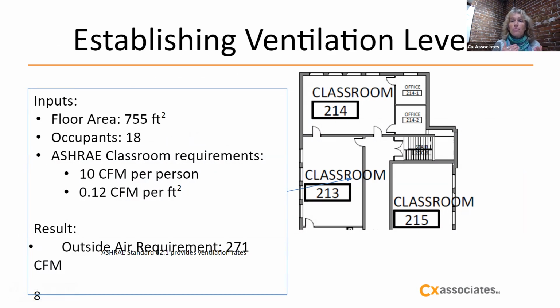ASHRAE has established a calculation form that determines how much outside air is required, dependent on the floor area of your space, the number of occupants you have in your space, and what type of space you have. So for example, if you are a gym, you're going to require more ventilation because people are breathing heavily and harder, and it's getting propelled faster, versus a classroom or even a theater where people are just more sedate. So what ASHRAE has is a calculation for that space type.